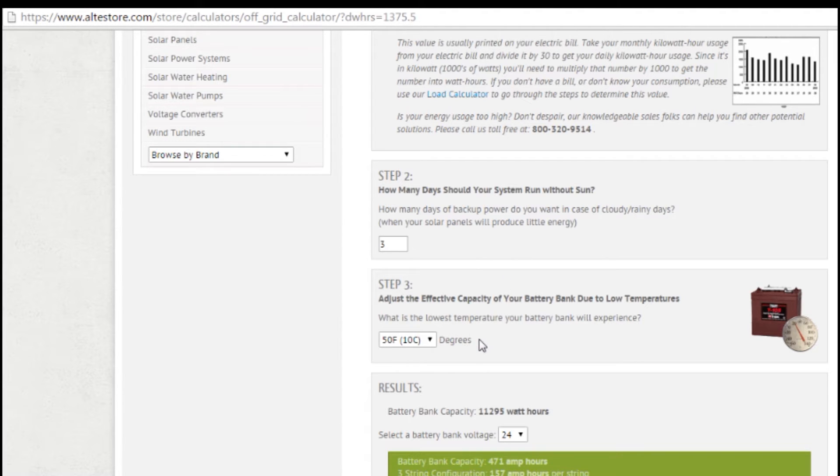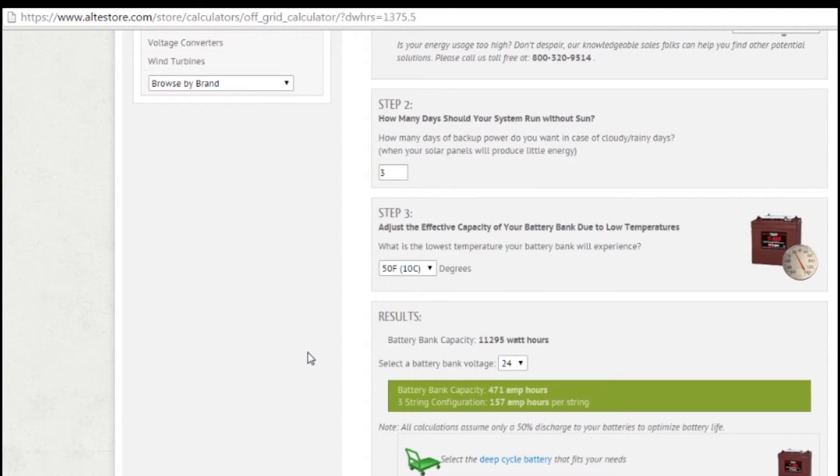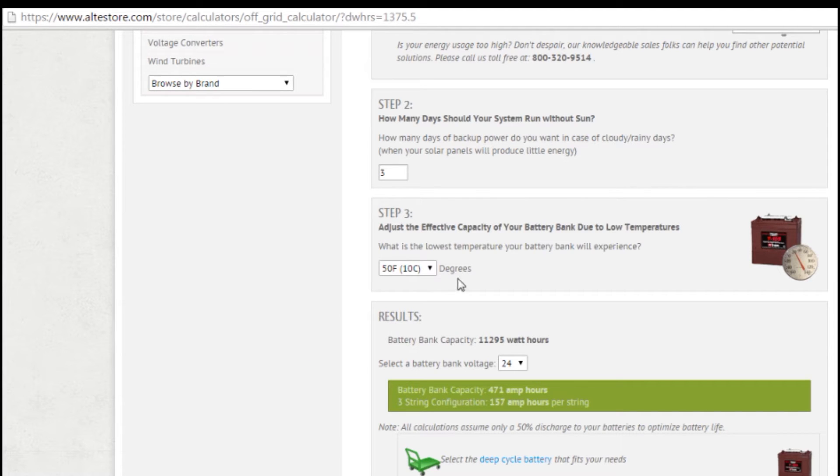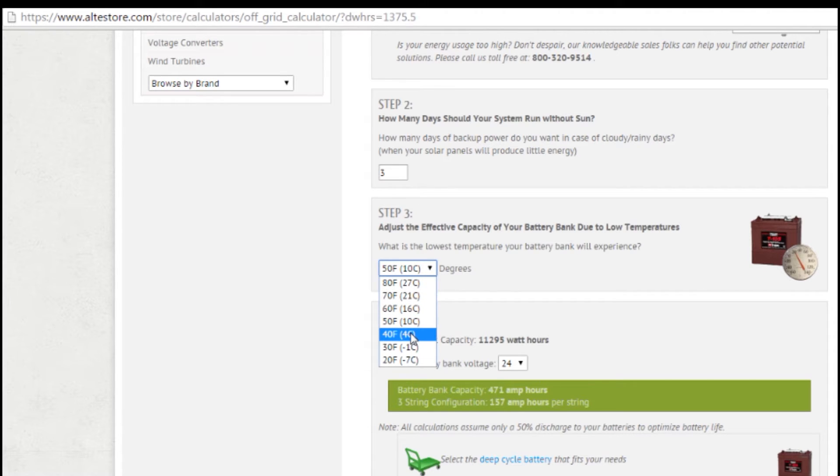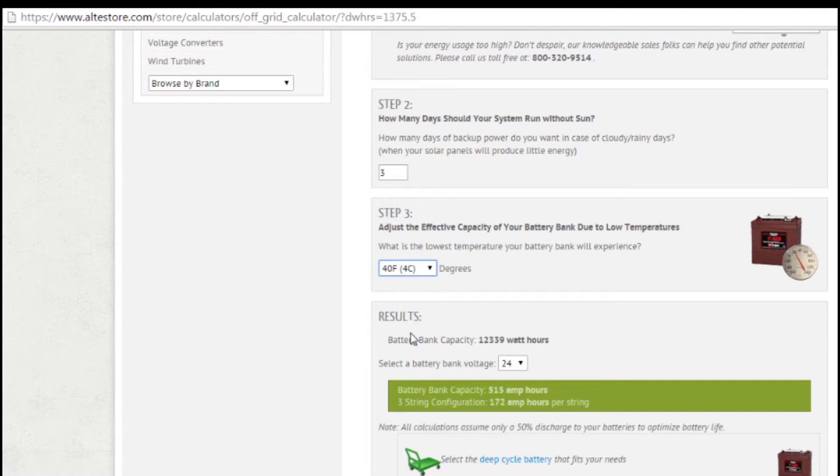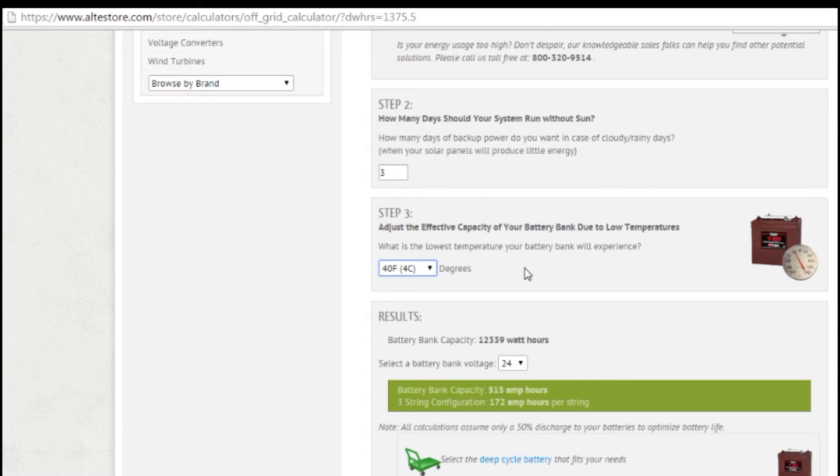So the next step is what temperature you're going to be storing your batteries in. Now, battery amp hour capacity is rated at 80 degrees Fahrenheit. So if you're going to be storing them in a room that's going to be cooler than that, and odds are pretty good you would, you would select what temperature you're going to be storing it in. For instance, if I'm storing it in my garage, it might get down to 40 degrees out in the garage. So I'm going to select 40 degrees, and that will automatically calculate in any temperature derations I need to accommodate the fact that when a battery is colder, it's going to be able to hold less power than if it's warm.